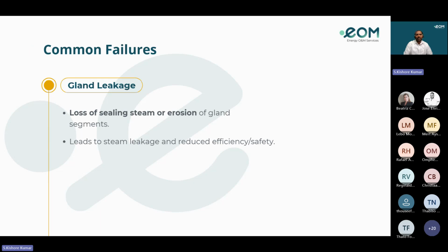And one more common failure is gland leakage. Gland leakage occurs because of loss of sealing or erosion of gland segments, which leads to steam leakage and reduced efficiency, and it also raises safety concerns. The following are the causes of gland steam leaks: worn or damaged seals, improper gland steam pressure, shaft misalignment, and wrong clearances.